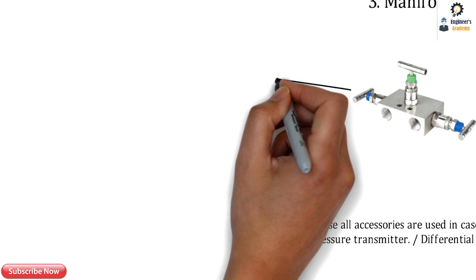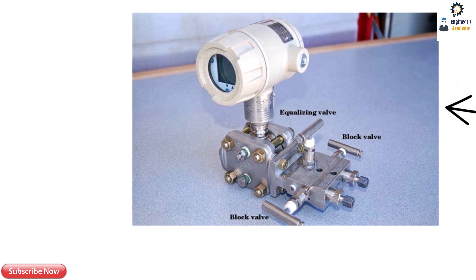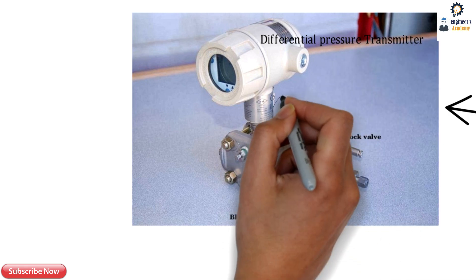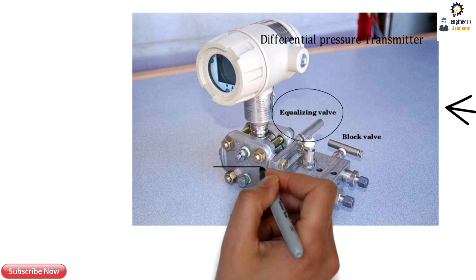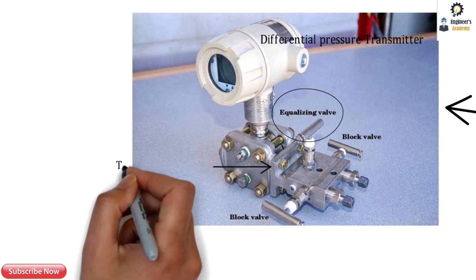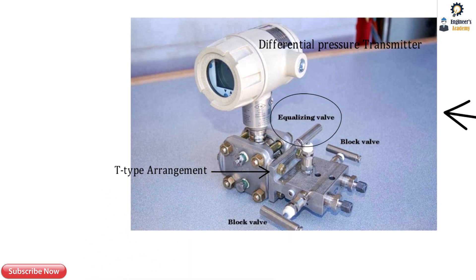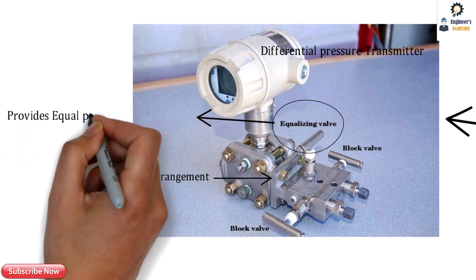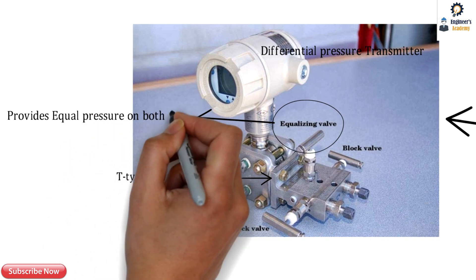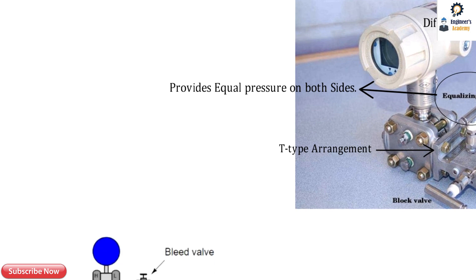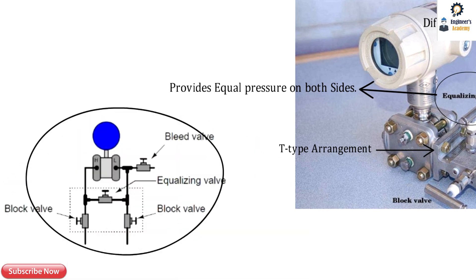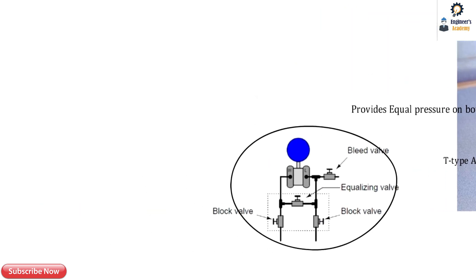The three-way manifold is used for differential pressure measurement. Here, a pressure transmitter is fitted with the three-way manifold. There is an additional equalizing valve along with two block or isolation valves, arranged in a T-type configuration. The equalizing valve provides equal pressure on both sides — the high pressure side and the low pressure side — which is essential for differential pressure measurement.